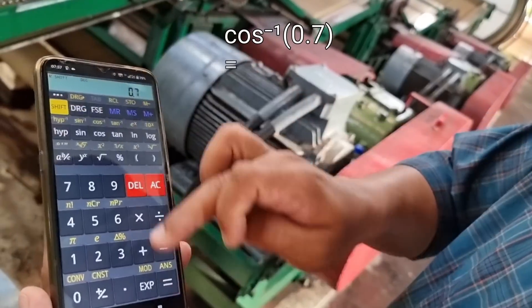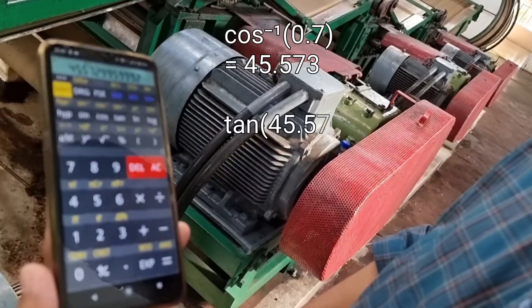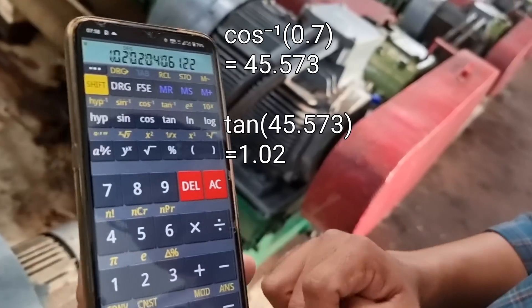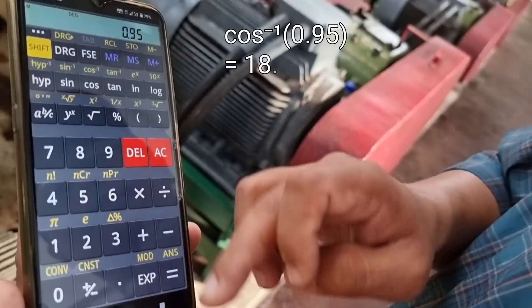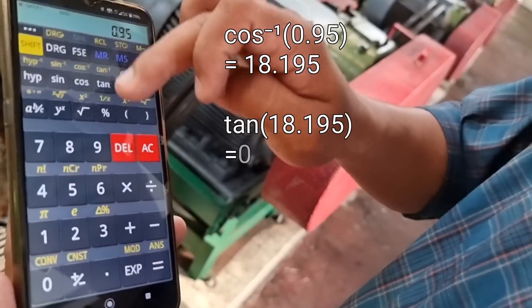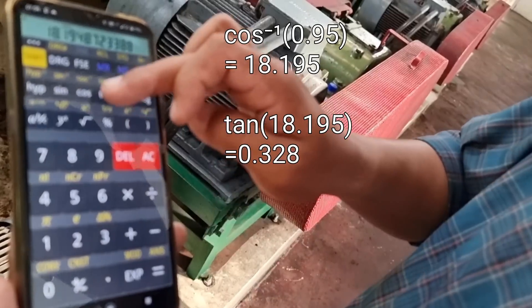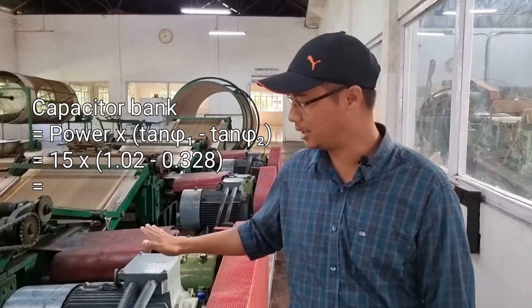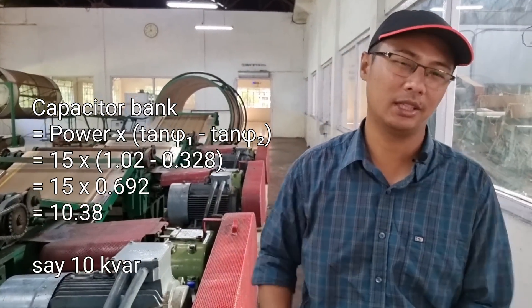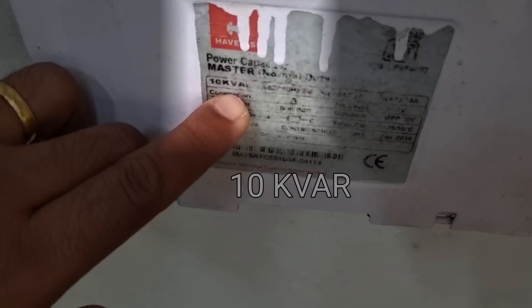Take 0.7, find the cos inverse to get the angle, then take the tan of that angle. For 0.95, do the same — cos inverse then tan. Subtract tan φ2 from tan φ1 and multiply by the motor rating of 15 kilowatts, and you get approximately 10.38 kVAR. Coming over here, you can see the capacitor bank rating is 10 kVAR, so this matches up to this motor.